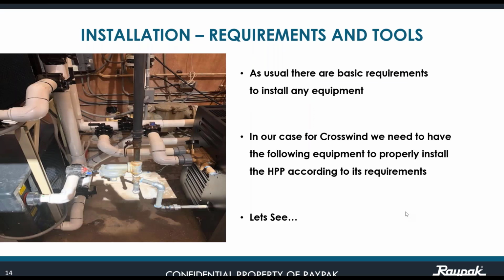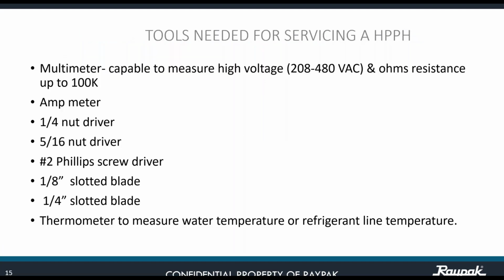As with every installation, there are requirements, and these are really basic requirements. For our Crosswind, we need to have the following equipment to install properly the unit. We need a multimeter capable of measuring high voltage, 208 to 480, and ohms resistance up to 100K. We need an amp meter, a 1/4 nut driver, a 5/16 nut driver, number 2 Phillips, 1/8 slotted blade, 1/4 slotted blade, and a manual thermometer to measure the water temperature or refrigerant line temperature.